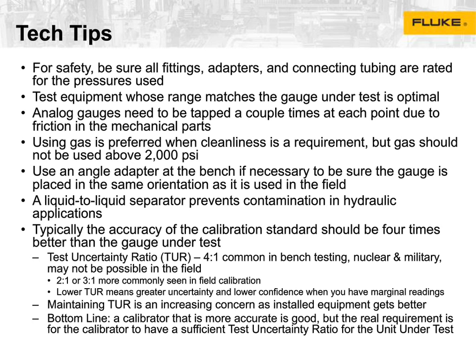And then the last part we're going to talk about here is the accuracy of the calibration standard. When you verify things like gauges or transmitters or any other piece of pressure equipment, how accurate does your calibrator need to be? Traditionally, a long time ago, it was as high as 10 to 1. Your calibrator needed to be 10 times more accurate than the unit that was under test.